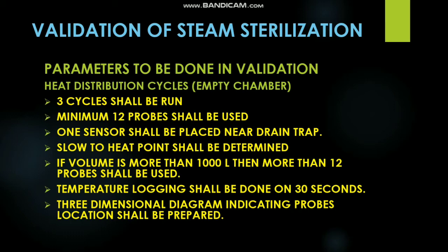So the reading shall be recorded every 30 seconds, and a 3-dimensional diagram indicating the probes and the location of probes shall be prepared as a part of documentation, and this diagram shall also be used in your validation study document. Along with that, we can also take pictures of the probes' location.